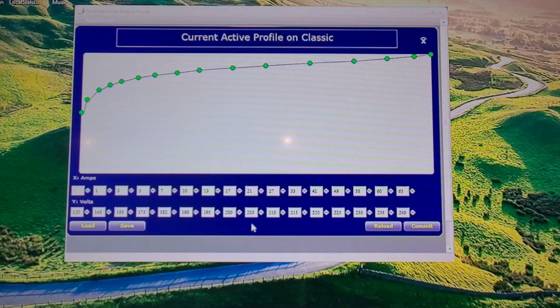I've been blowing up the 220 volt SSRs when I had this wind curve set at 200 volts. It was still killing those SSRs. I took apart the SSR and they're rated for 300 volts, the IGBTs in them, so it must have some pretty high spikes.